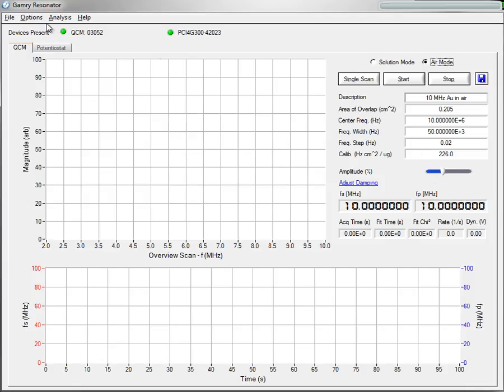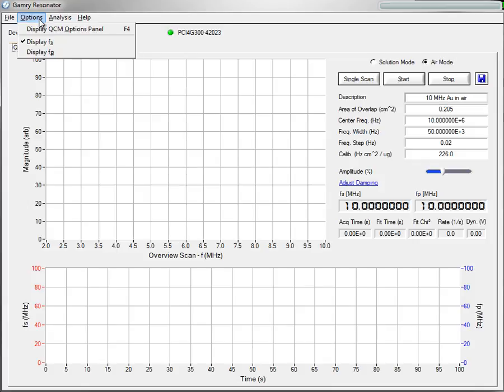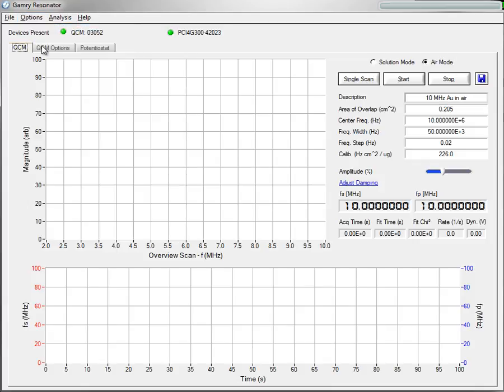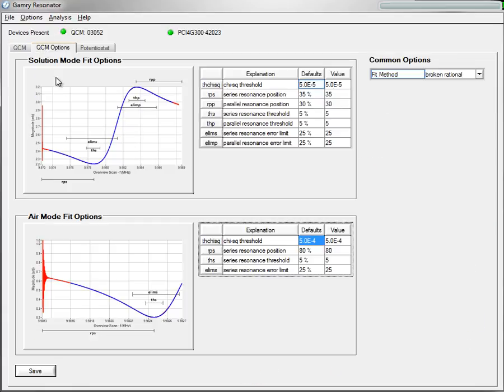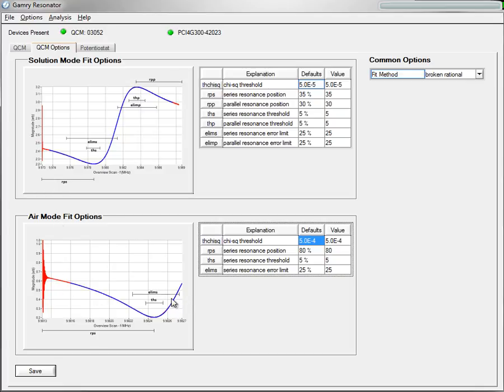If you're curious how the Air Mode works before we start it, one of the things you could do is click on Options and display QCM Options panel. That brings up this panel. Now, what we do in Solution Mode is we scan through the whole frequency window. What we're going to do in Air Mode is we actually only scan approximately half the window and then fit our data to that window.